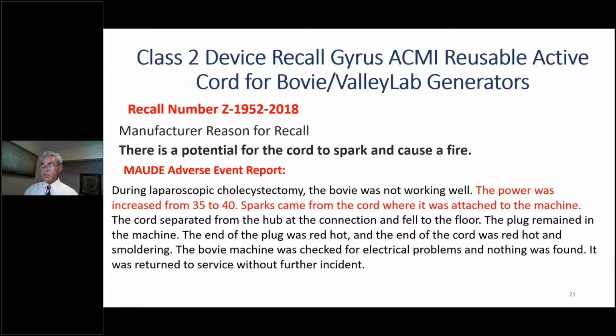The Bovie was not working well. The power was increased from 35 to 40. A spark came from the cord where it was attached to the machine. One of the issues was that there weren't enough conductors left at the end of it - the last couple of strands caused a lot of energy to go through the remaining wire, creating a spark that fell on the floor.